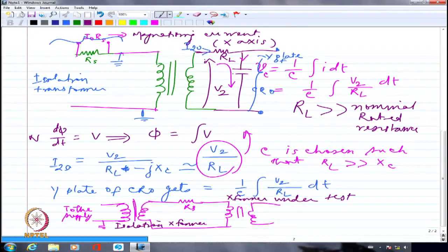The primary and secondary of the isolation transformer are isolated from each other. There is no connection directly between the ground of the primary of the isolation transformer and the secondary of the isolation transformer. Now I don't have to worry. All the grounds are separate. Right? So I don't have to worry that something is really going wrong with the entire connection. That will not happen. So normally the BH loop experiment will never be conducted without an isolation transformer. The isolation transformer is only meant for making sure that nothing is short circuited inadvertently without knowing. Some ground is connected to some other ground and then you will just see a Diwali. You don't want that to happen. As simple as that. That's the reason. Right? Got it? So much for the open circuit test and BH loop of the transformer.